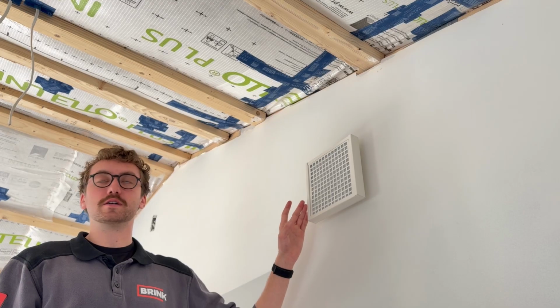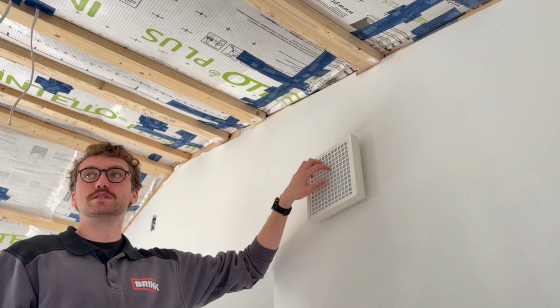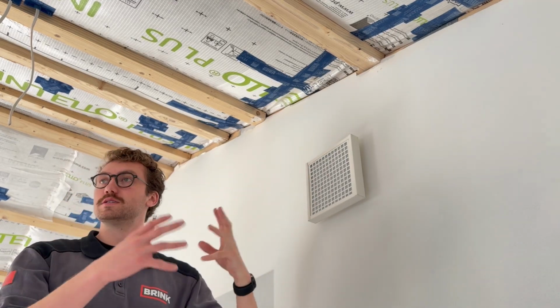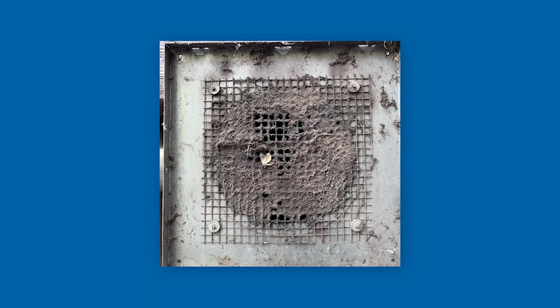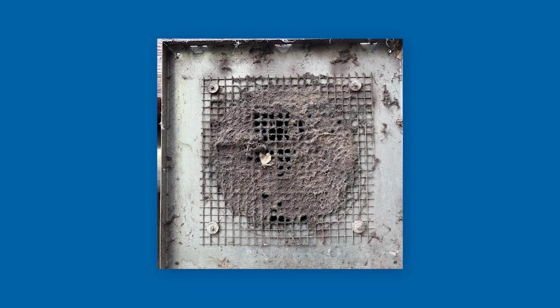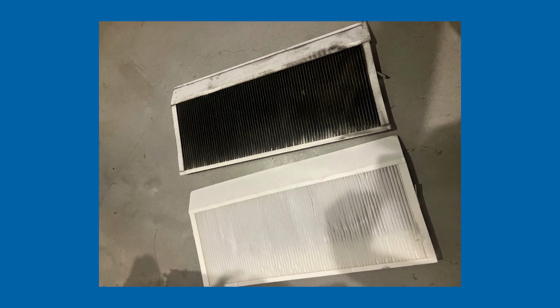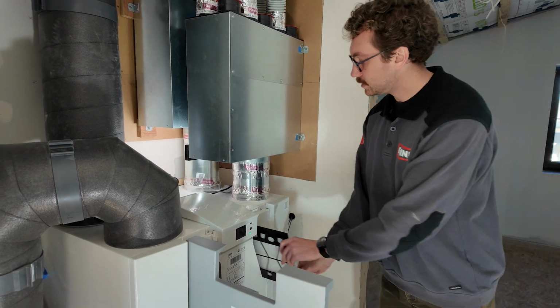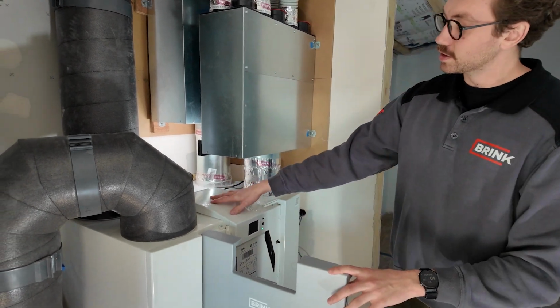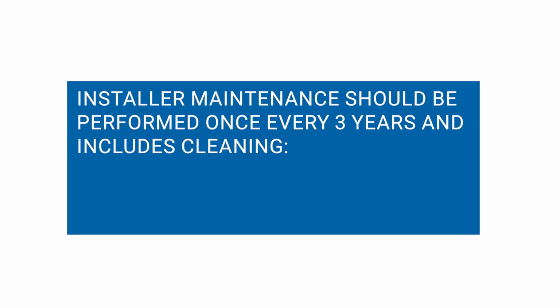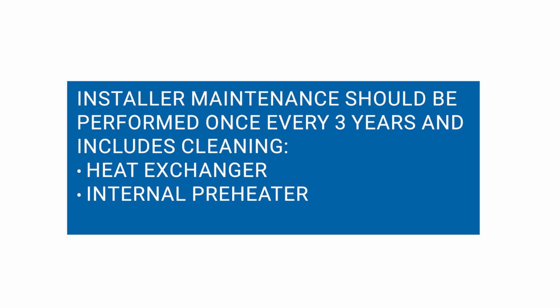Providing homeowner education about system use and routine maintenance is good practice. By keeping the intake grill clear of debris and regular changing of filters, the unit will perform well for years to come. Installer maintenance should be performed once every 3 years and includes cleaning the heat exchanger, internal preheater, and fans.